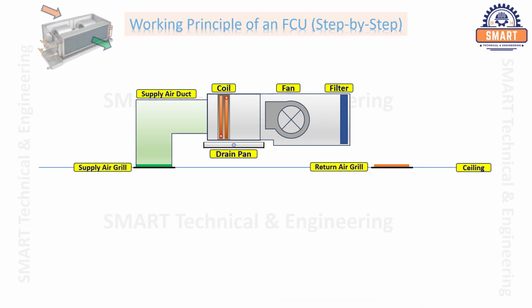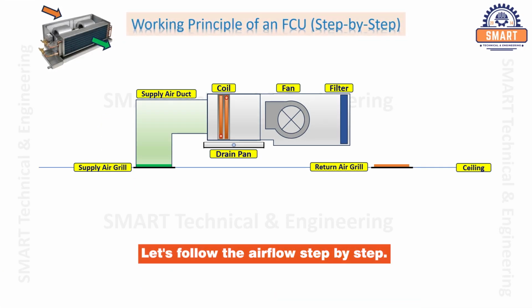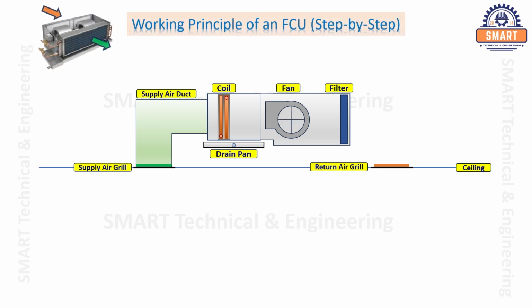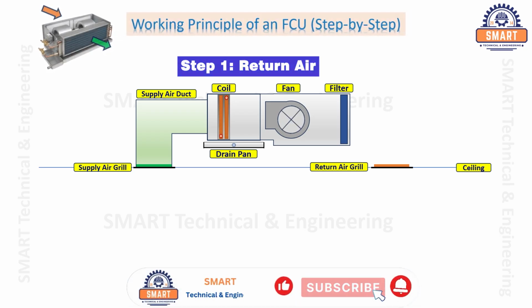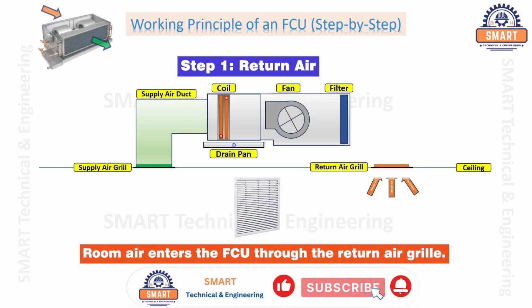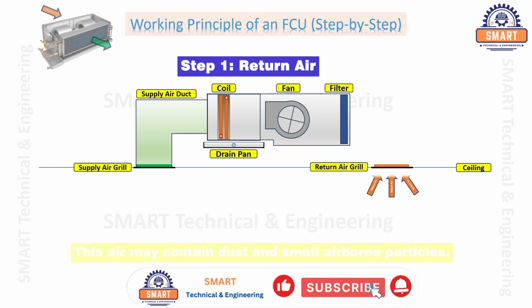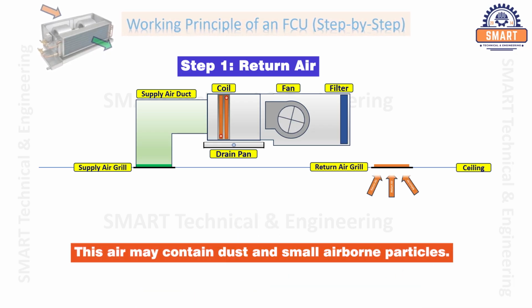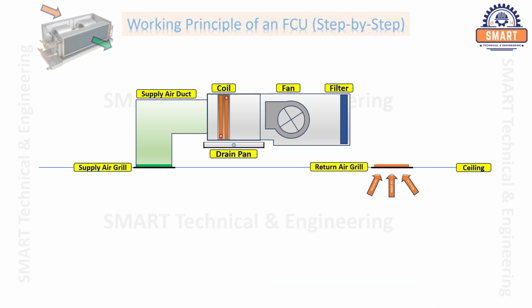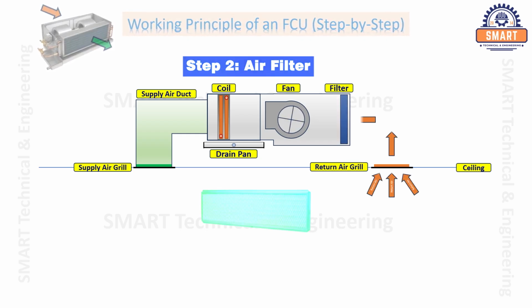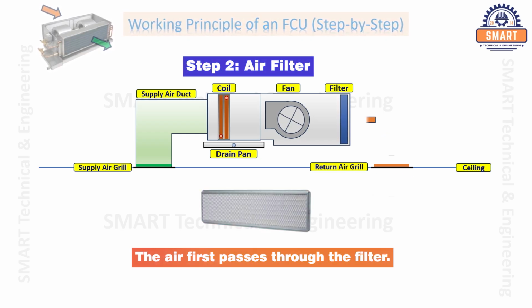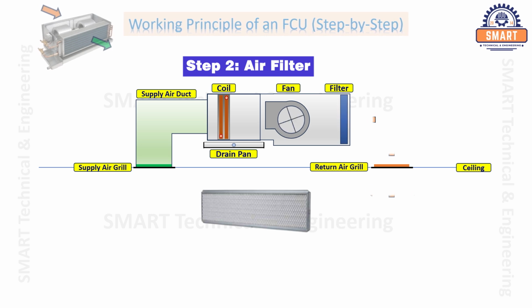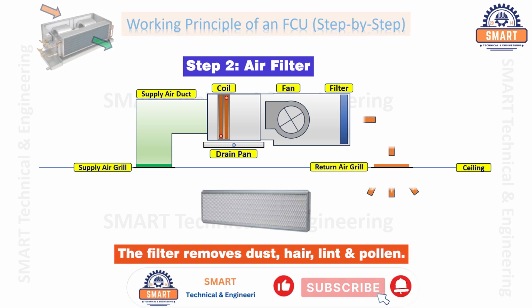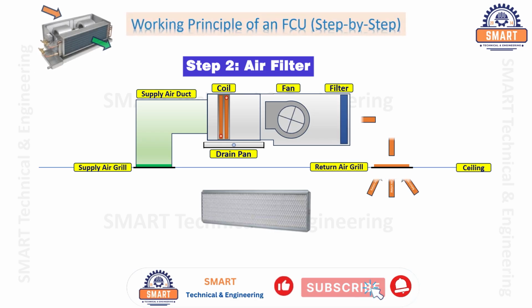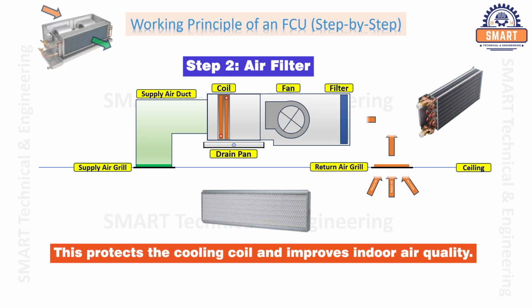FCU working principle. Let's follow the airflow step by step. Step 1. Return air. Room air enters the FCU through the return air grill. This air may contain dust and small airborne particles. Step 2. Air filter. The air first passes through the filter. The filter removes dust, hair, lint, pollen. This protects the cooling coil and improves indoor air quality.